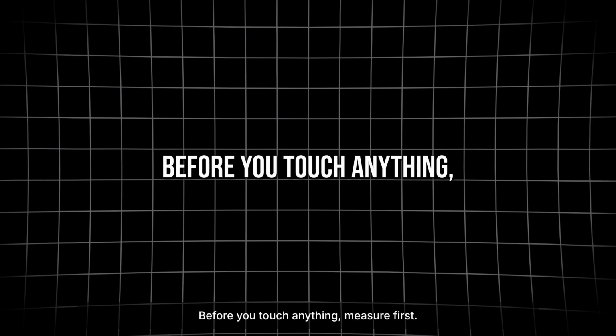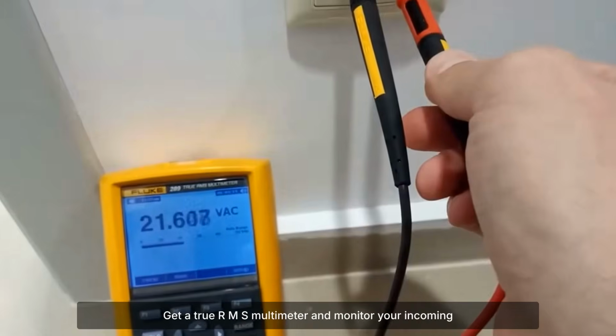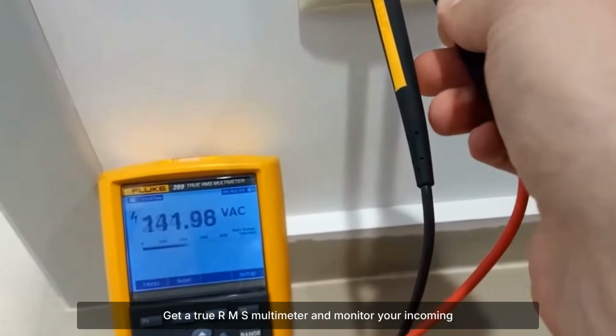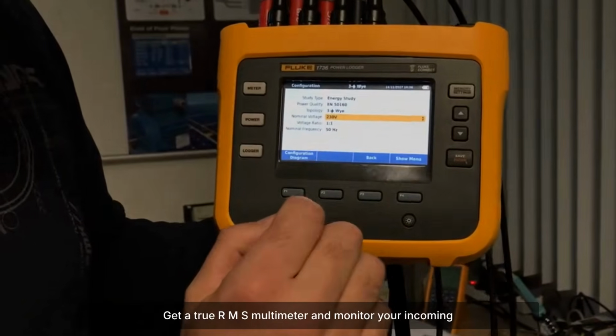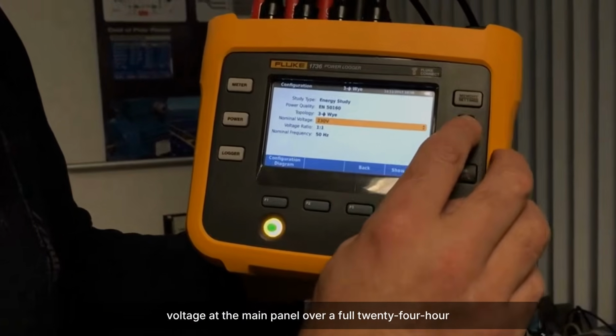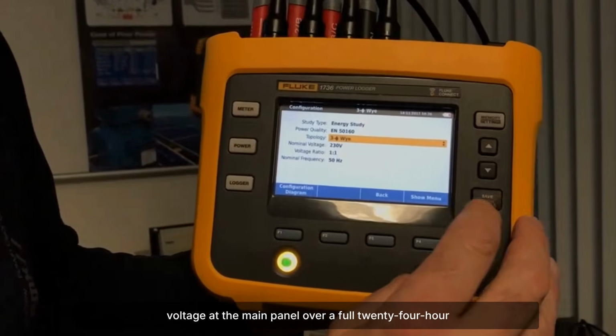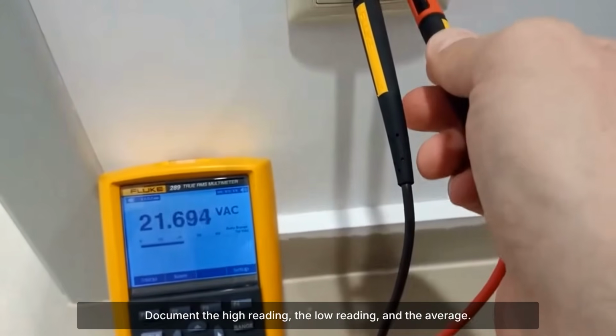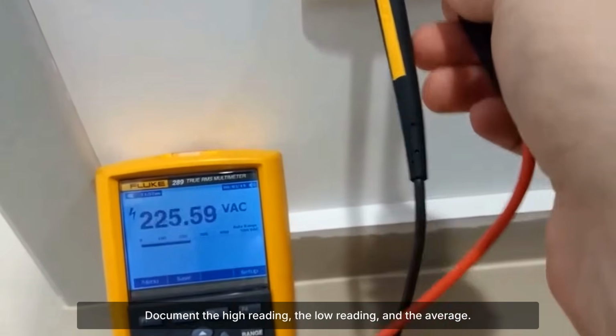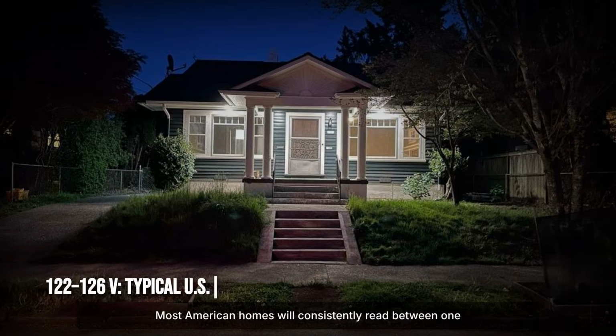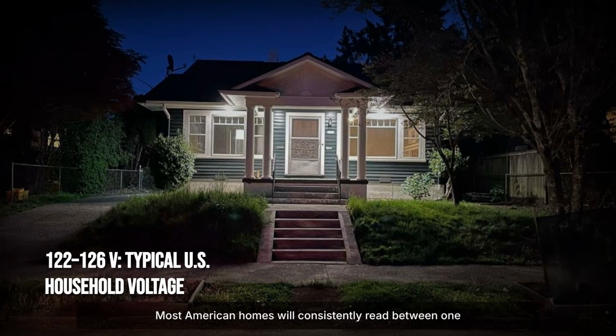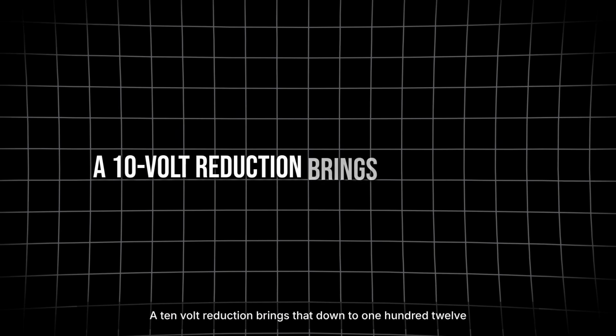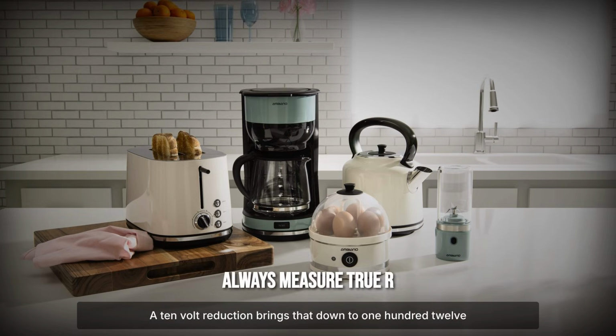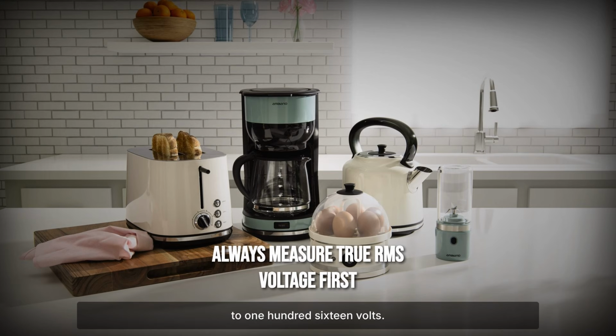Before you touch anything, measure first. Get a true RMS multimeter and monitor your incoming voltage at the main panel over a full 24-hour cycle. Document the high reading, the low reading, and the average. Most American homes will consistently read between 122 and 126 volts. A 10-volt reduction brings that down to 112 to 116 volts.